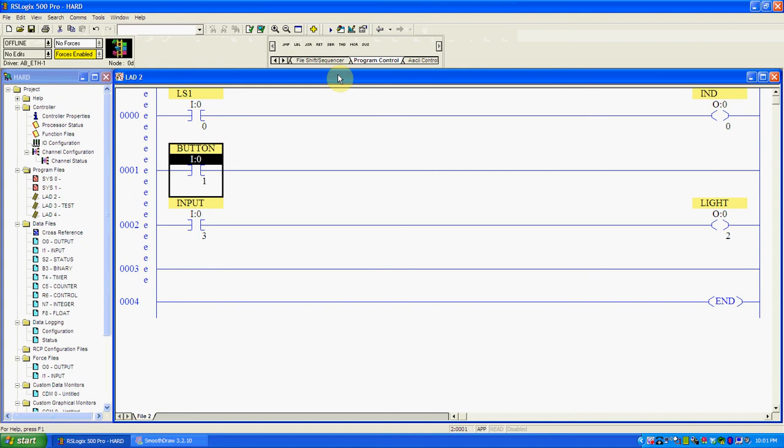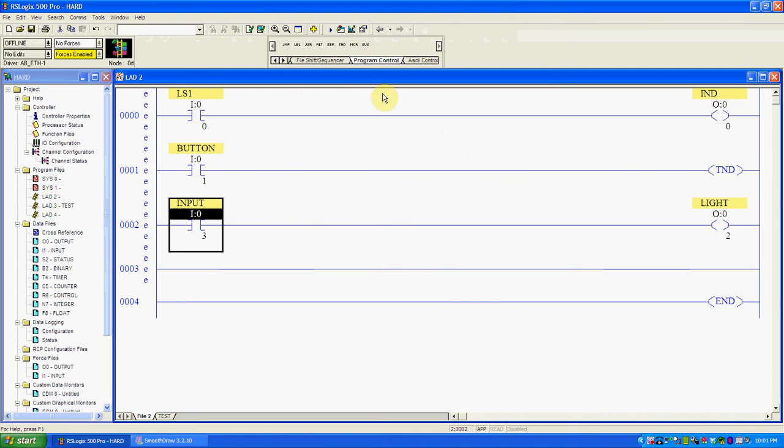Another option that's sometimes used is this one called temporary end, where you're basically now saying if this button's pressed, this is no longer the end. The end is now here. So it would never run this. If it thinks this is the end of the logic, I've ended the logic early. And this could be used here, or I could go into a subroutine and put it here, so that if you go into a subroutine and something goes horribly wrong, machine crashes, whatever, you can say just end now. Is another one of the commands that we could use.